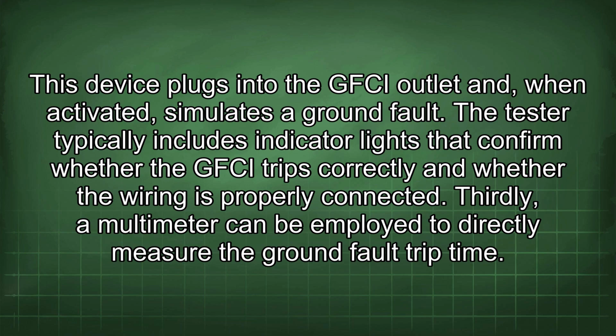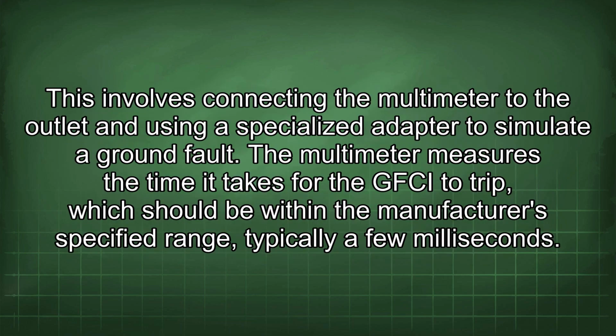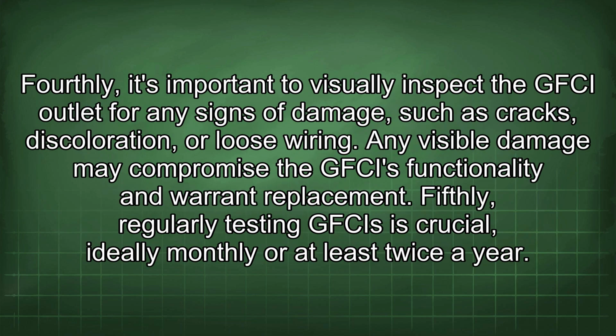Thirdly, a multimeter can be employed to directly measure the ground fault trip time. This involves connecting the multimeter to the outlet and using a specialized adapter to simulate a ground fault. The multimeter measures the time it takes for the GFCI to trip, which should be within the manufacturer's specified range, typically a few milliseconds.